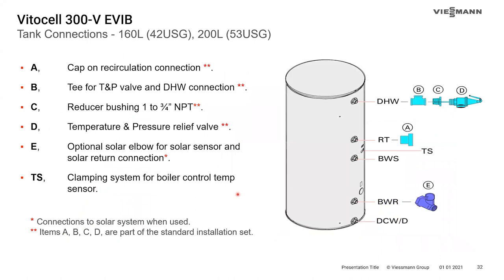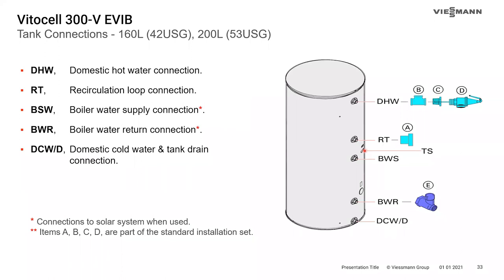Looking at tank connections: items A, B, C, and D come shipped with the tank as part of the standard installation set. A is the recirculation tap cap, B is the T that allows you to install the pressure-temperature and pressure relief valve, with domestic hot water connection out the top. E is an optional solar elbow for threading a sensor well and connecting solar return. DHW is domestic hot water, RT is your recirculation loop connection, and you have boiler water supply and return. Domestic cold also doubles as a drain.